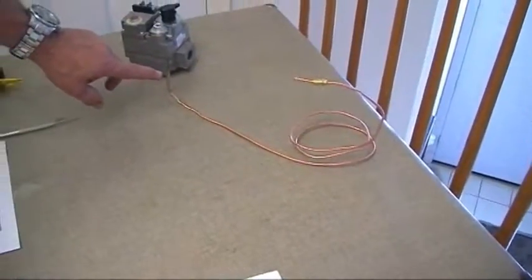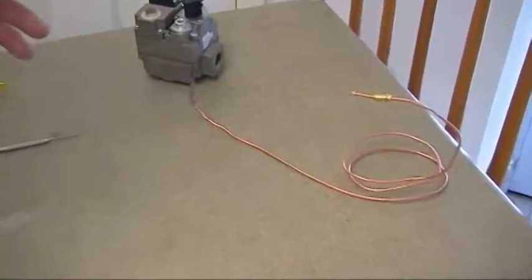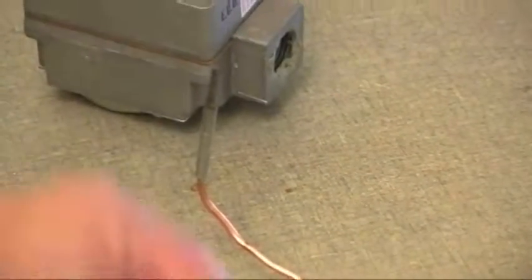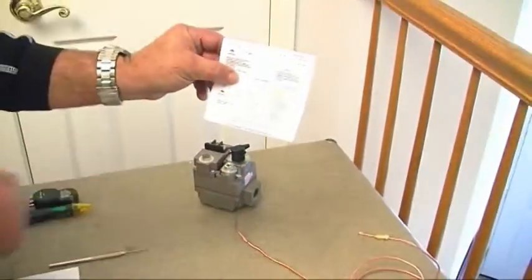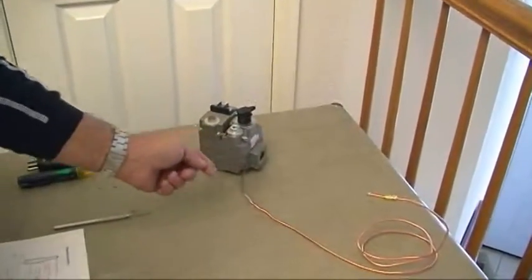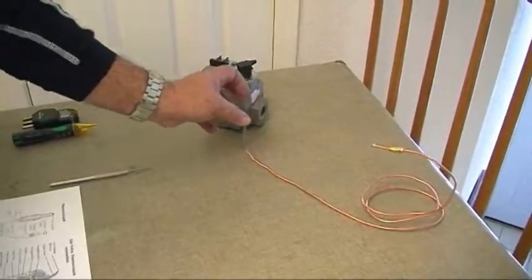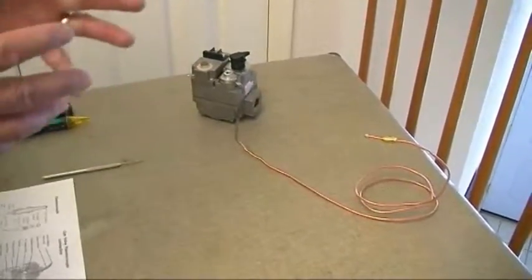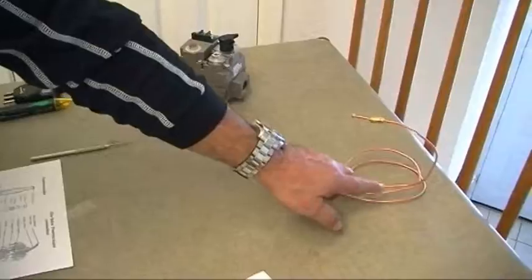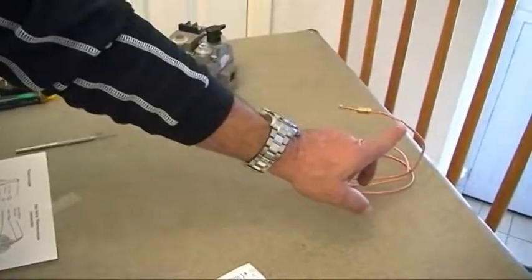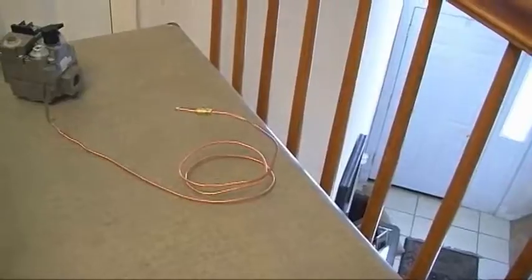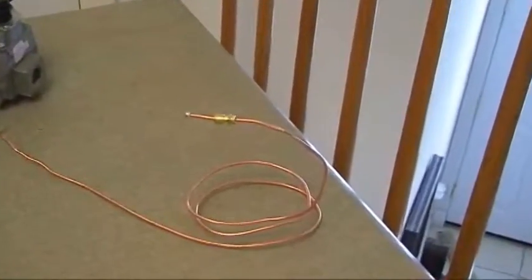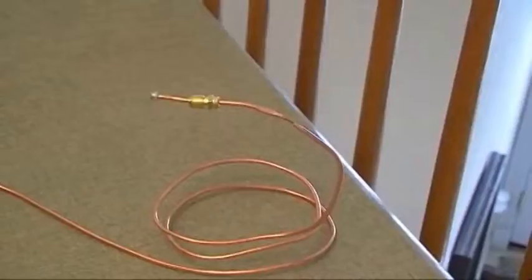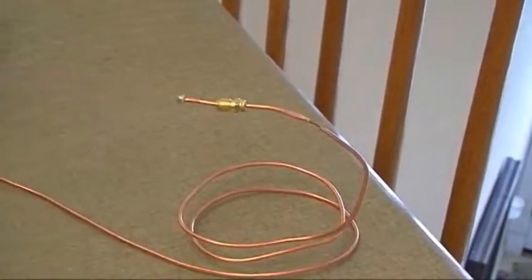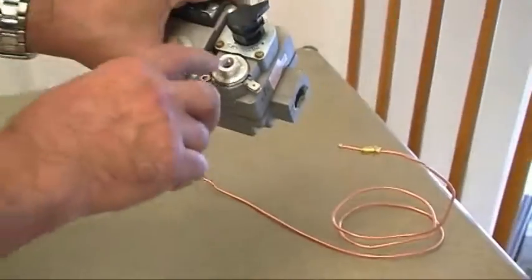Inside of this section on the inner area is a dissimilar metal, which is called the cold junction. When the hot junction is heated, as the manufacturer requests that you heat it in the first half inch, that is 1/2 inch right there, that's where the flame should hit, and then it creates millivolts through the dissimilar metals. You have your copper sleeve that comes around, and then you can see where you have a copper wire that is inside of the copper sleeve. It's called the inner wire lead. You have your attaching nut, you have a lock washer, and you have your tin-plated contact, which makes contact with the gas valve at this point.